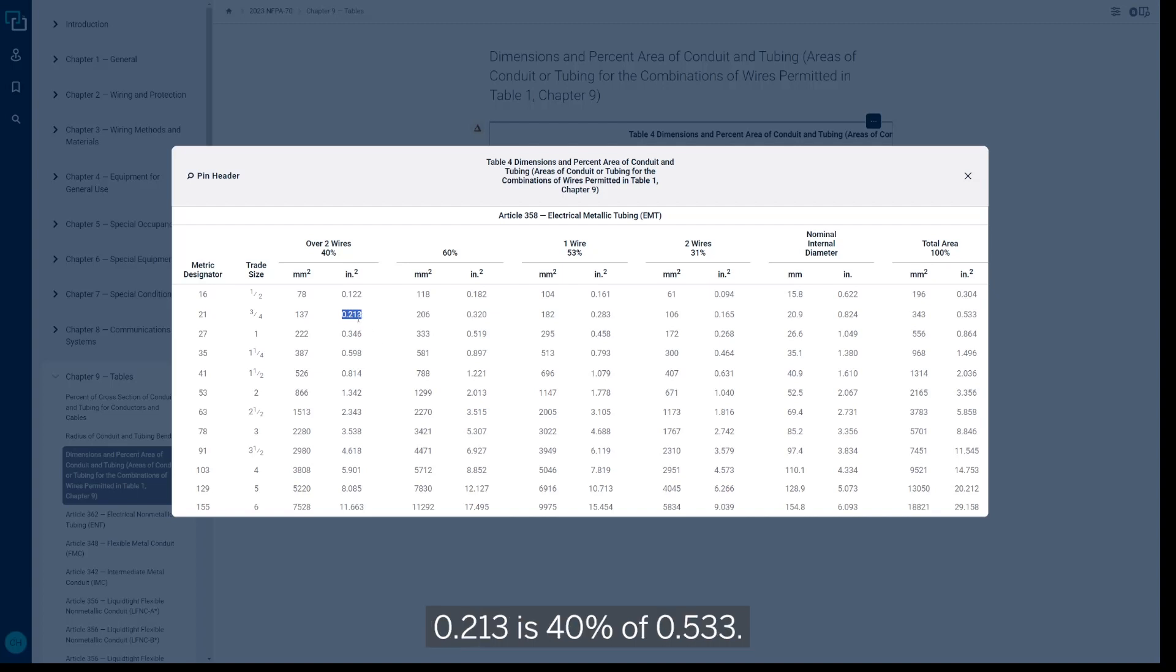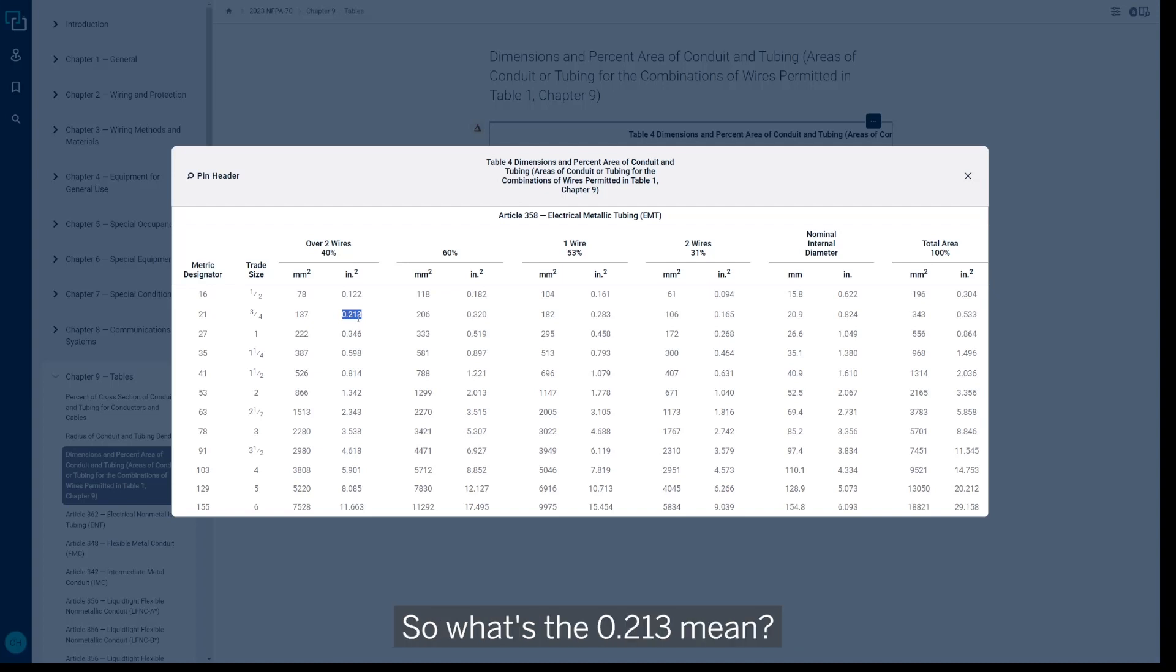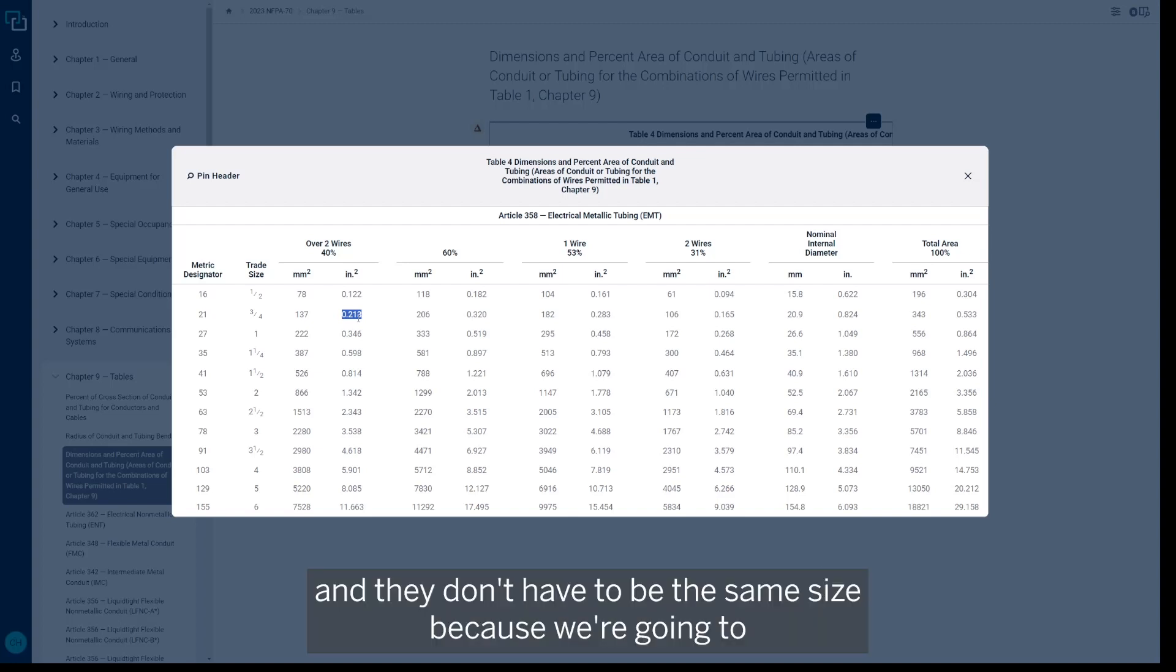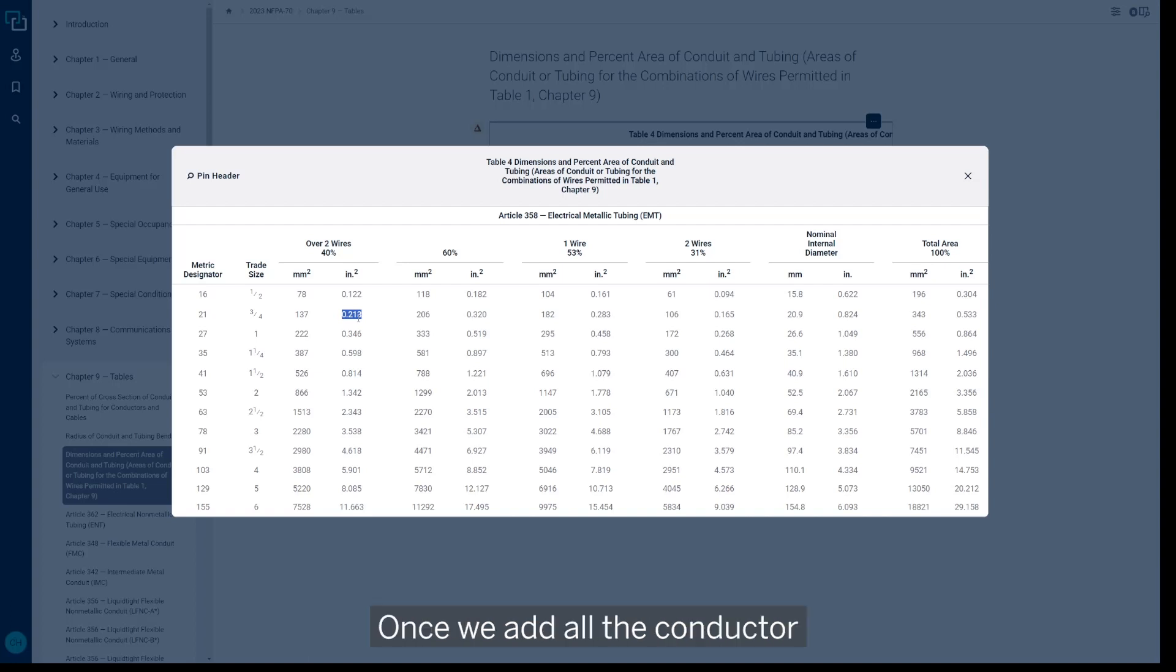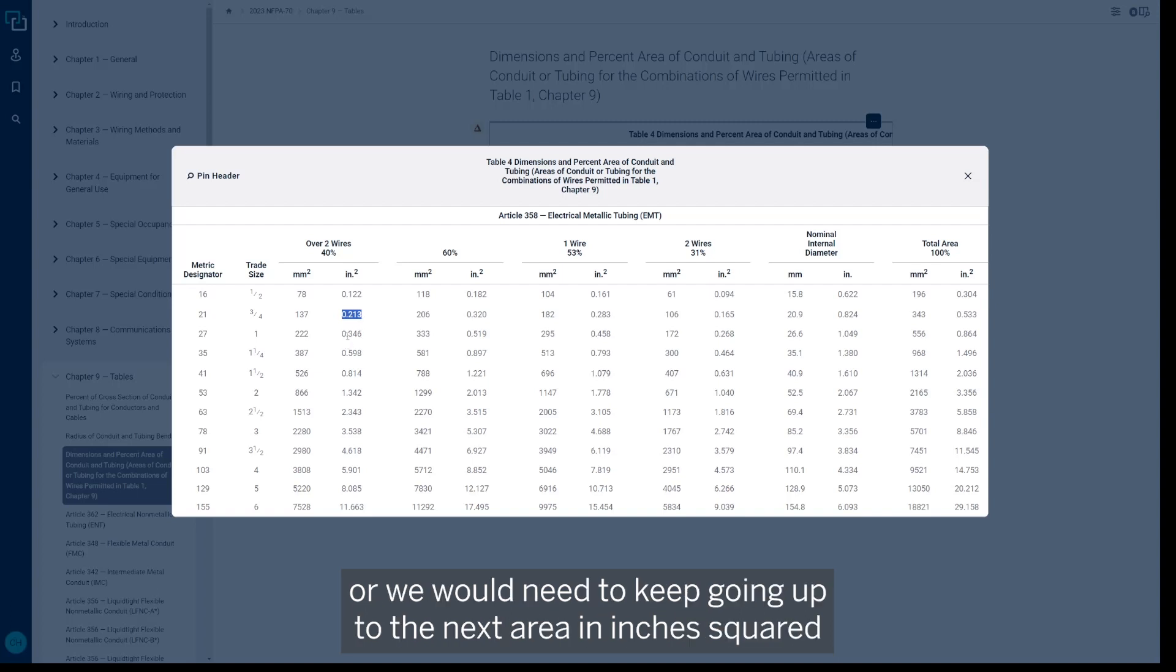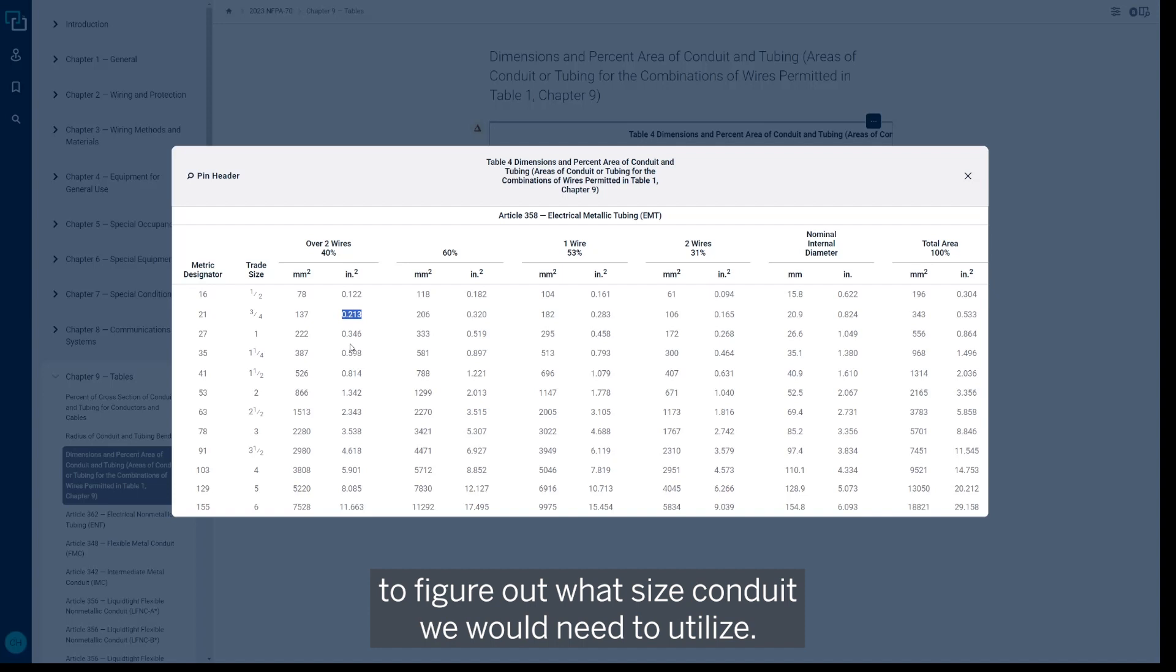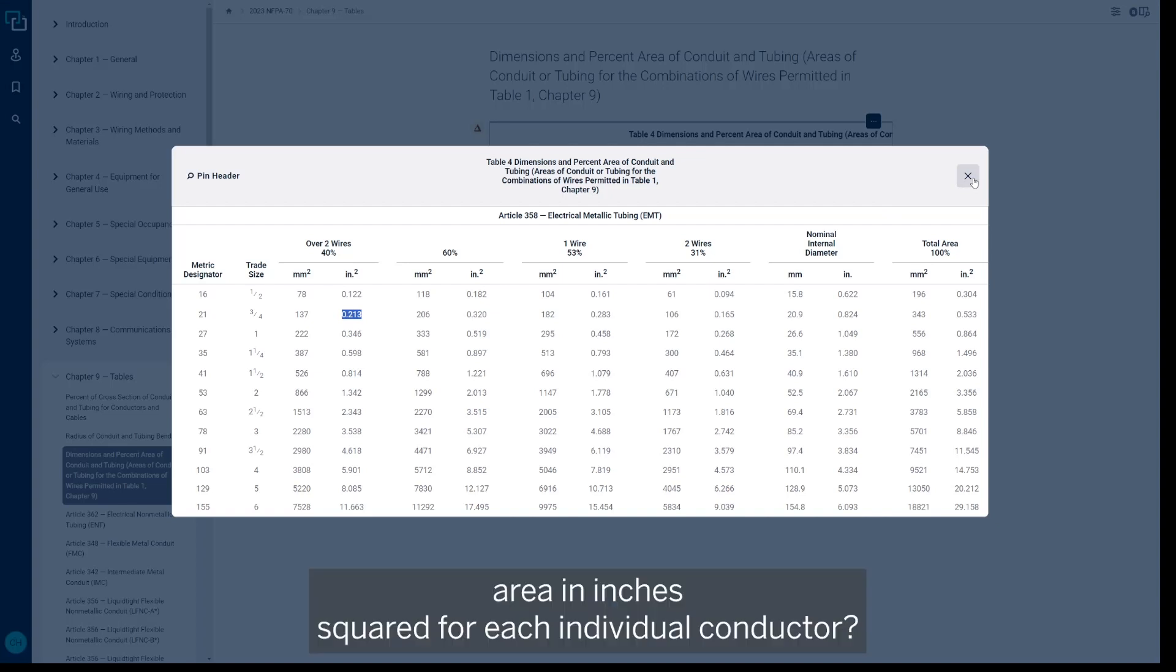So it's already done the calculation for us in order to do that. So what's the 0.213 mean? It means we can take all our individual conductors' sizes—and they don't have to be the same size because we're going to pick them individually and then add them up together. Once we add all the conductor areas together to get that total value, it would have to be less than 0.213 in order to utilize that three-quarter inch conduit in that application. Or we would need to keep going up to the next area in inches squared to figure out what size conduit we would need to utilize.